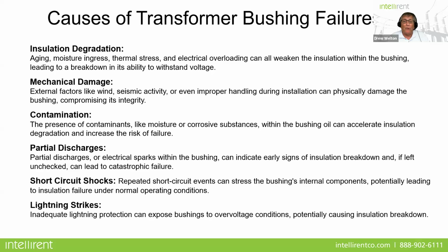If you have bushings in a petrochemical or in a harsh environment, this could also create contamination issues and lead to premature failure. Partial discharge, or electrical sparks within the bushing, can indicate early signs of insulation breakdown. And if you leave these unchecked, this can lead to catastrophic failure. Short circuit shocks: repeated short circuit events can stress the bushing's internal components, potentially leading to insulation failure under normal operating conditions. And down here in Florida, where I live, we're the lightning capital of the world. So if you continually expose bushings to lightning or overvoltage conditions due to lightning, that can cause insulation breakdown as well.